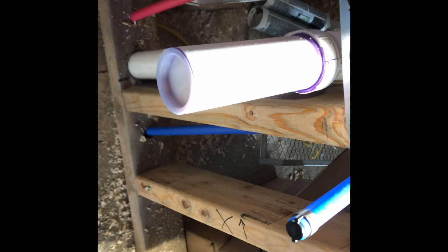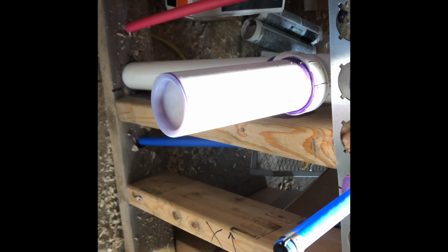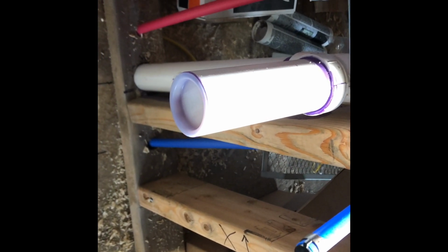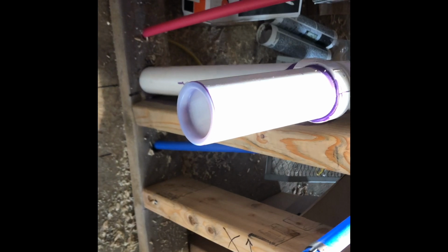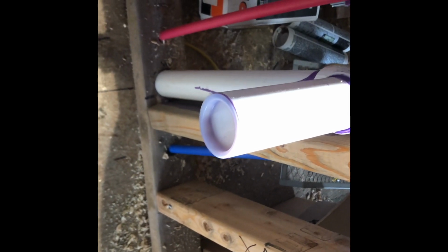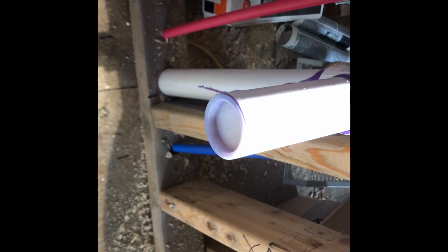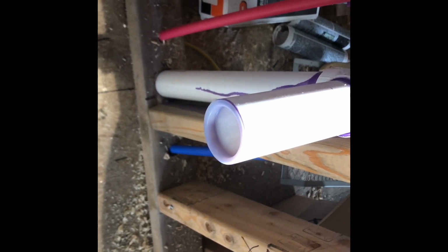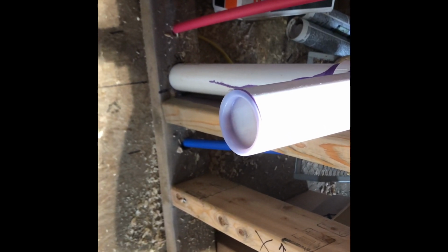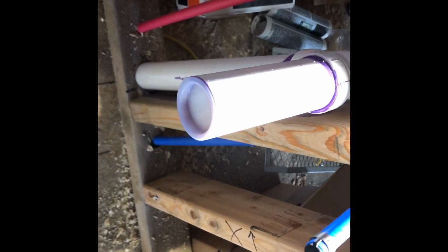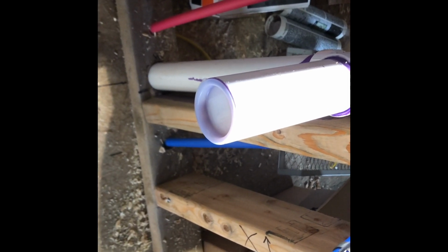We've got a leak in our vent system, our drain vent piping, which is going to need to hold 5 psi for the inspection to pass. So when you're looking for these leaks, you need to be thorough, and there are several ways you can go, but one good way is get a quality leak detector. Yeah, you can use soapy water.